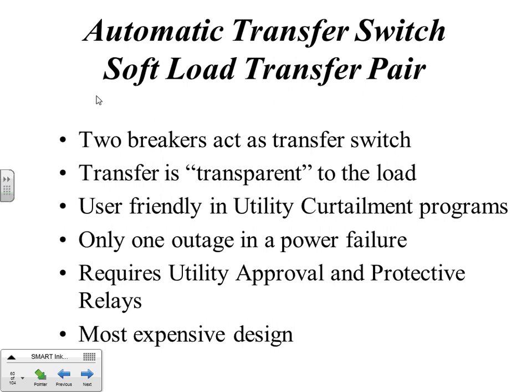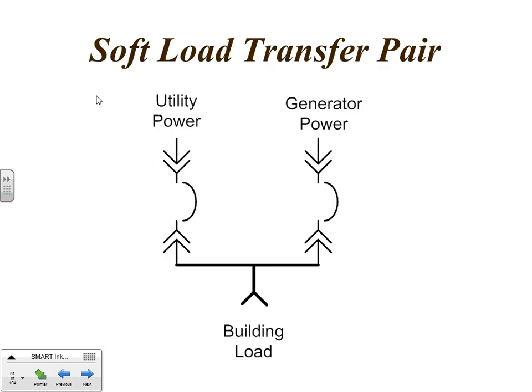It's user-friendly in utility curtailment programs. Again, the customer gets the flexibility of his load never getting interrupted, and it doesn't know anything's happened. And it definitely requires utility approval and protective relays. It's the most expensive design, but it offers you the greatest benefit as well. Very simple schematic here, showing electrically operated draw-out breakers. It's typically the way the system is designed.